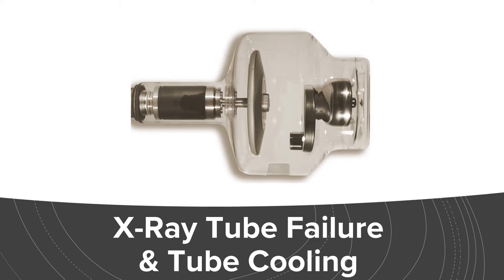We know that 99% of the energy in the incident electron beam can be converted into heat rather than x-rays, so it comes as no surprise that high heat is the number one cause of x-ray tube failure.